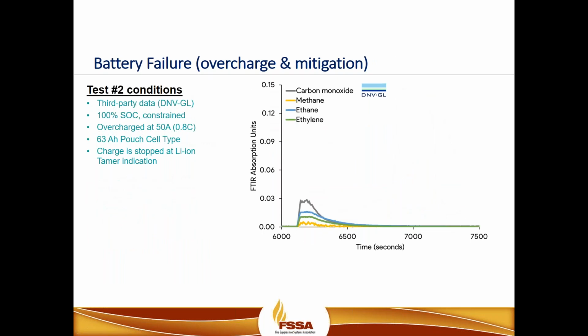In this second test here, we show an overcharging and a mitigation factor. So the battery, you'll see in this particular example here, carbon monoxide, methane, ethane, and ethylene are released in the space through off-gassing. This test represented an overcharging event. So earlier we discussed overcharging where you may not experience a rise in temperature, and that's primarily because overcharging occurs at a relatively low temperature.